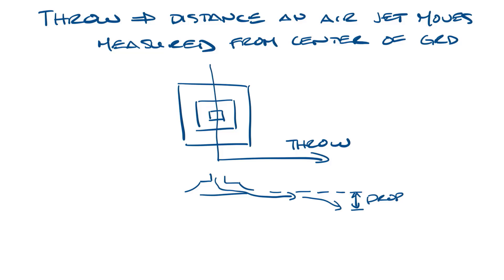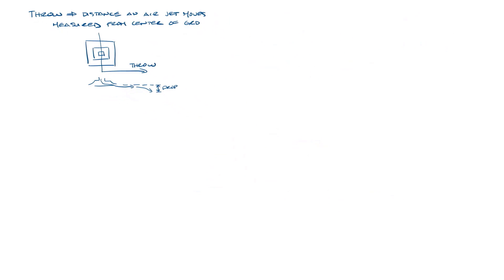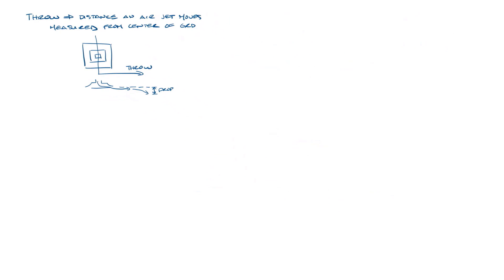Throw is measured at certain velocities. Per ASHRAE, we catalog throw at 150 feet per minute, 100 feet per minute, and 50 feet per minute.